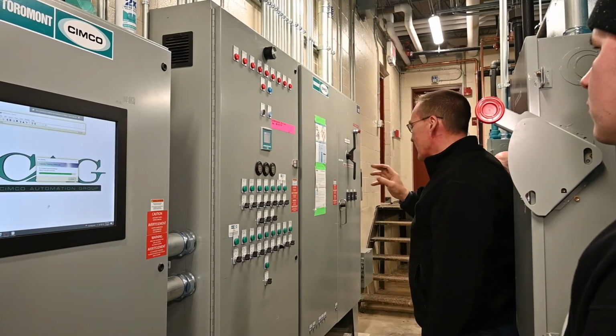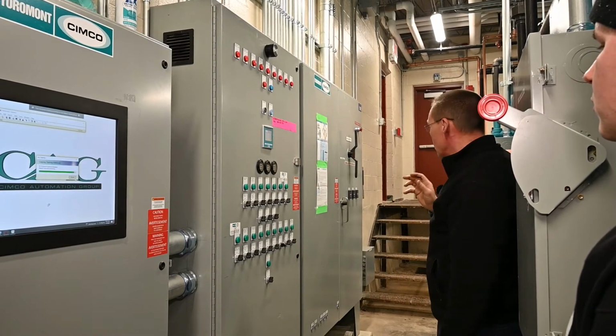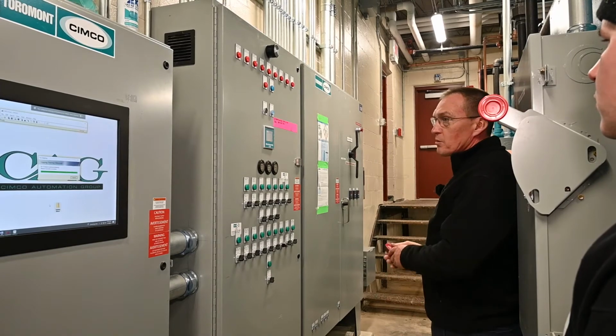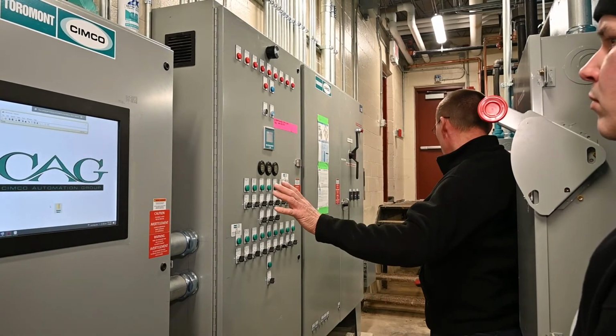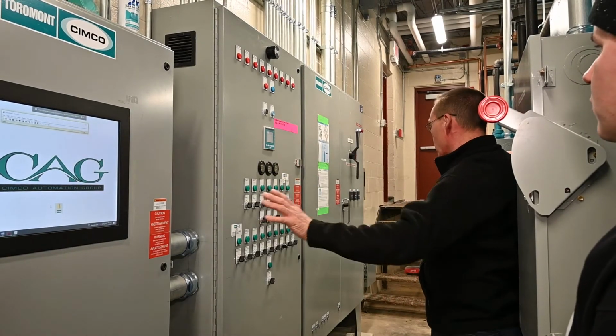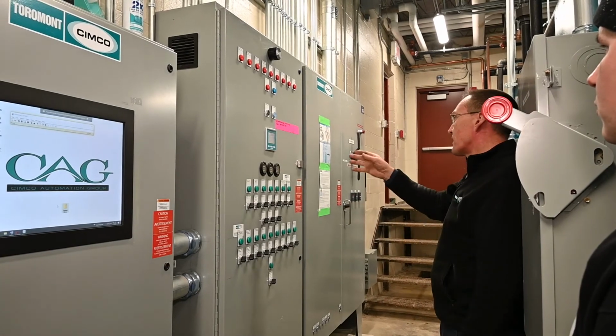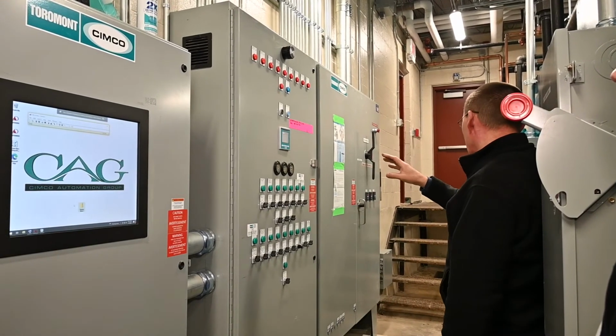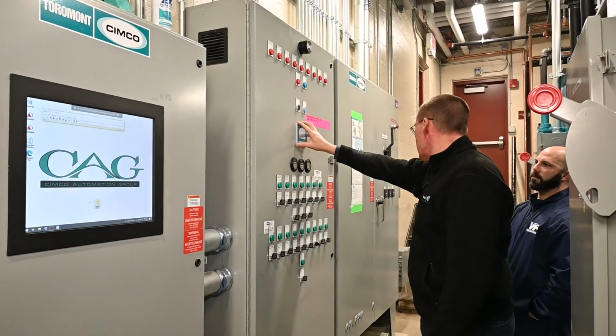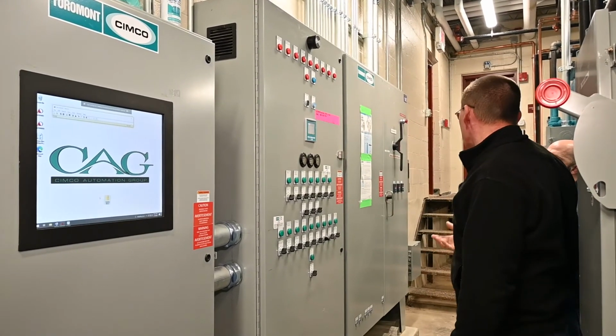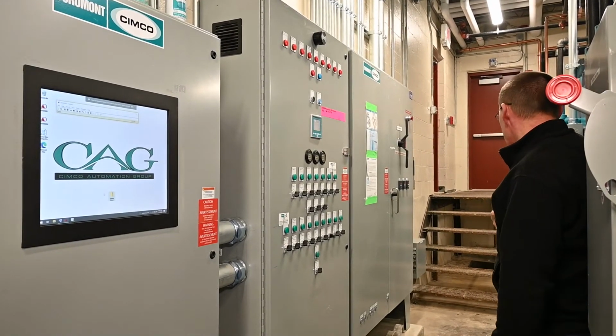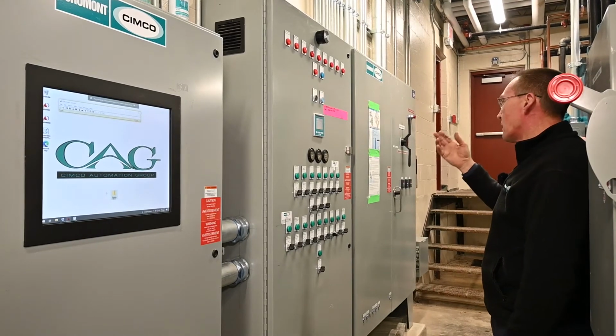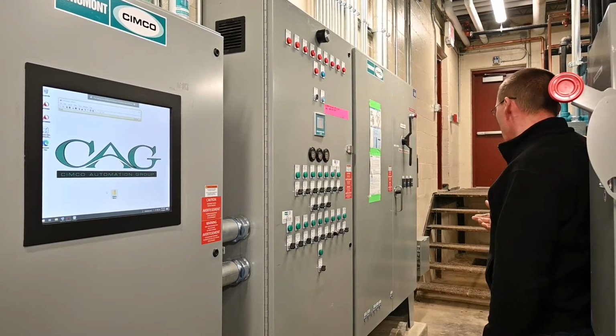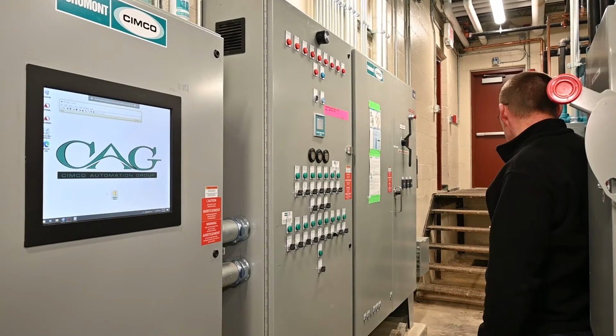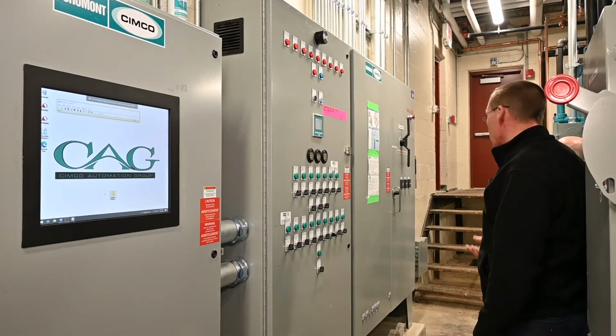Once there is an alarm latched into the system, the alarm has to be reset. Not only will you have an alarm within the computer, because the computer runs everything, you will then have to clear an alarm here on the Unitronics screen. And of course, call your service provider. We have the warranty for a year on this, so you're going to call us and let us know. We'll get up here, figure out what happened, and get it resolved.